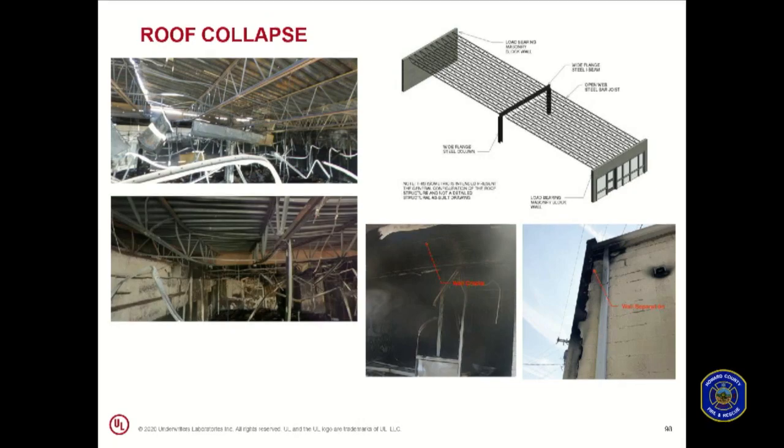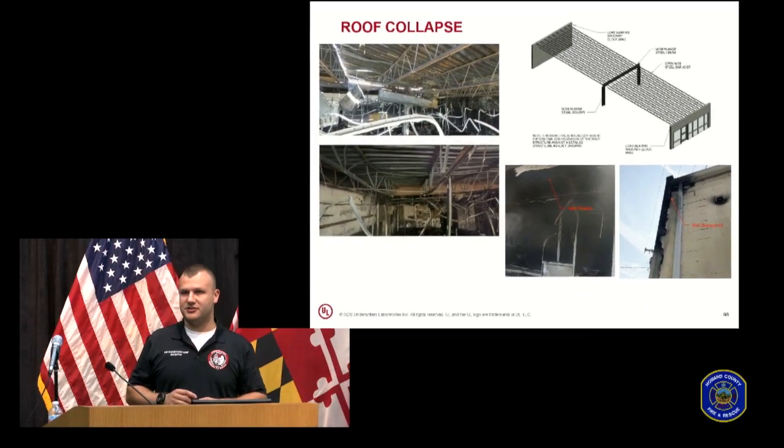You had a drop ceiling throughout the entire space, so you couldn't see them, but we know that as that fire gets going, that aluminum channel holding up the drop ceiling is going to warp. Those tiles will fall down, and now you've got fire exposure to actual structural members. So you see the damage there on the left-hand side. We didn't let these experiments go for all that long, and not every single one of them even transitioned to flashover.